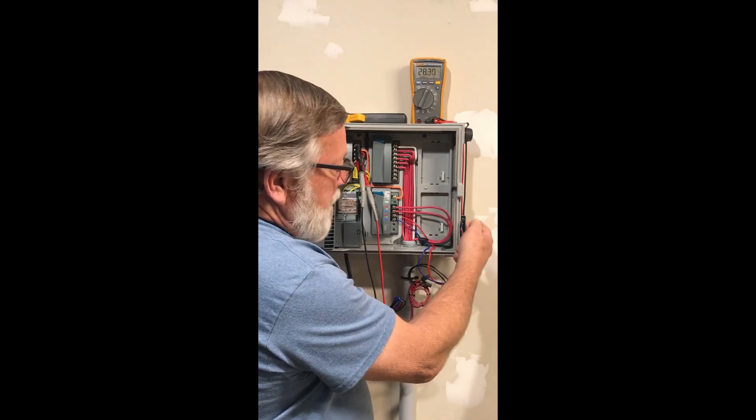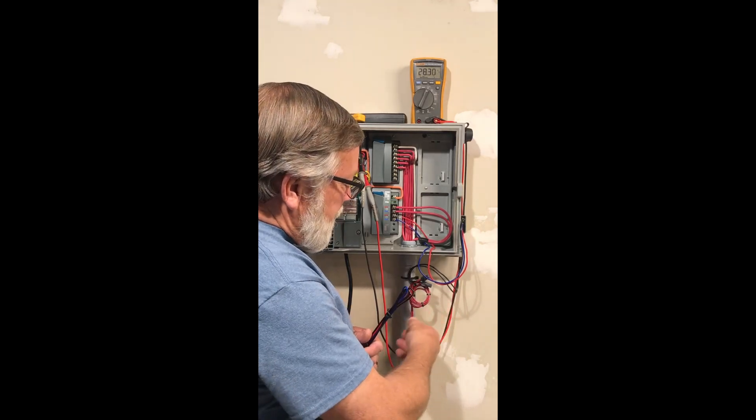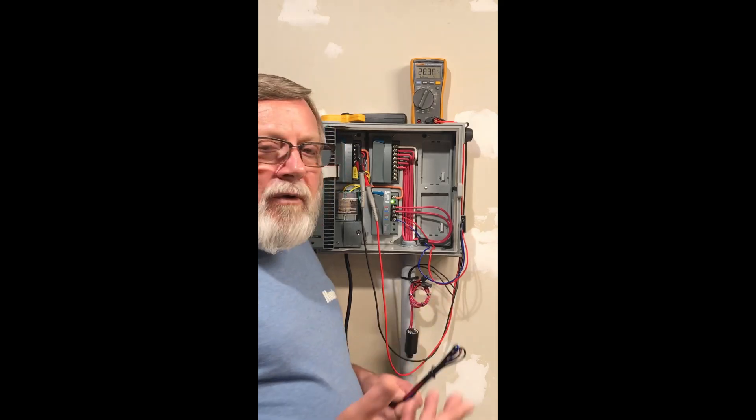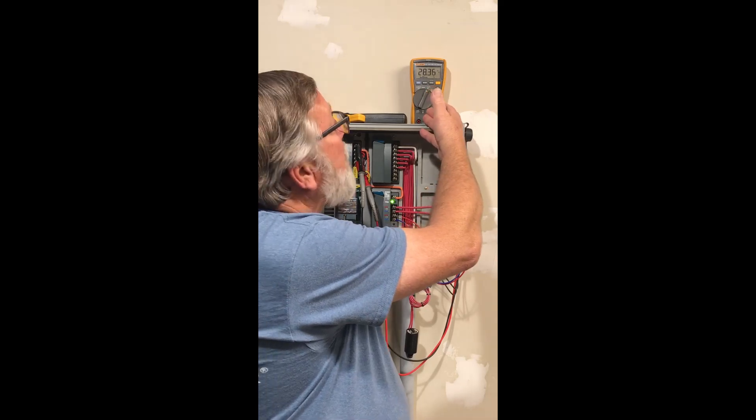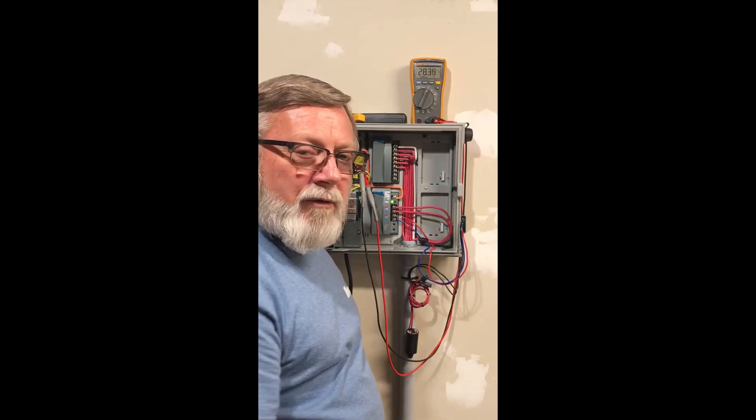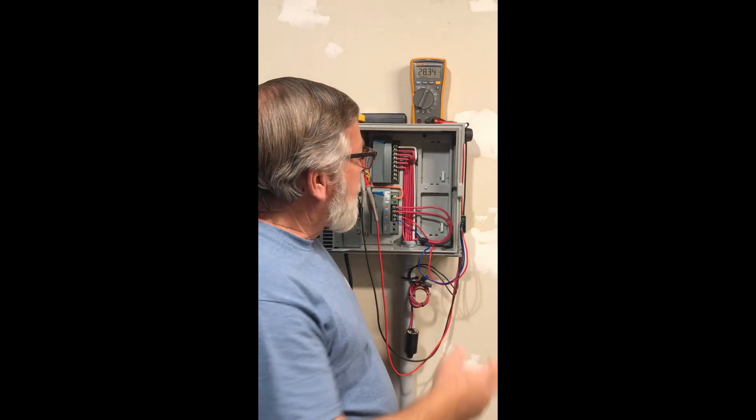If you do have both of these flashing but the solenoid is still not opening then you have something going on with the solenoid then you can check for voltage here. All this voltage I'm talking about is nothing special. I have just the standard 24 volt AC coming out of it 60 Hertz so my voltmeter should be able to read it all. No special tools just standard 24 volt AC 60 Hertz.